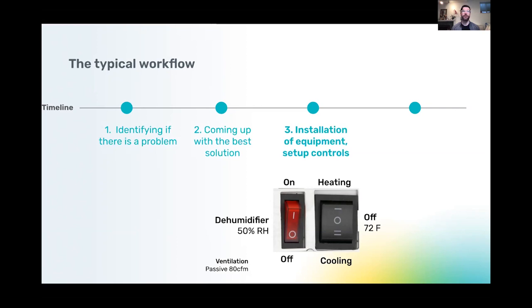Another one is installing dehumidifiers. Sometimes dehumidifiers can be installed incorrectly. There are various different types of installations. There's something called a dedicated return to supply. There's something called a return of the central air handler to supply. There is a supply to supply version of the installation. And there are some people who do what is not recommended, at least for certain types of dehumidifiers, which is a return to return installation of the dehumidifier.